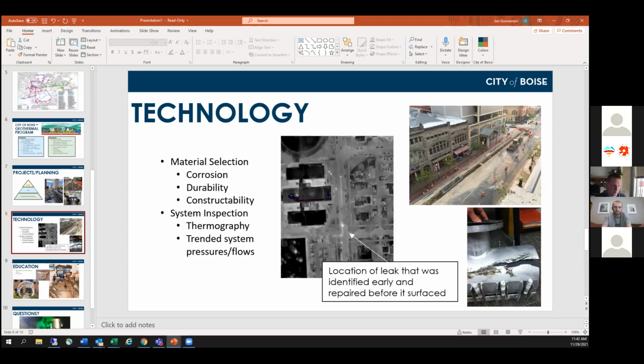Here's an example of one service tap we used for a period of time. This was specified as 316 stainless steel, which has a very minimal rate of corrosion. But this was pulled out after just 1 year, and we saw what's referred to as stress corrosion cracking. We actually had Boise State University do an entire material study, an engineering failure analysis report, on why this was happening.